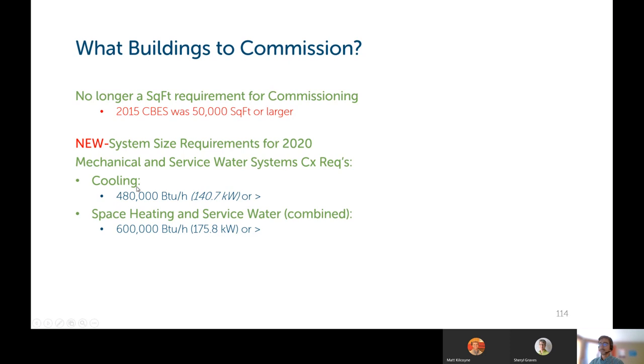So for a cooling water system or cooling system in general, 480,000 BTU per hour or more, you need to commission that. Or space heating and service water heating combined capacity of 600,000 BTU per hour or more will require commissioning.